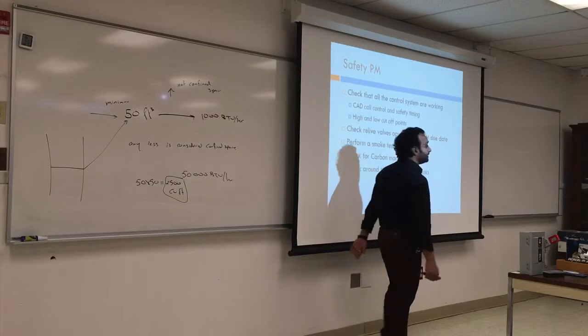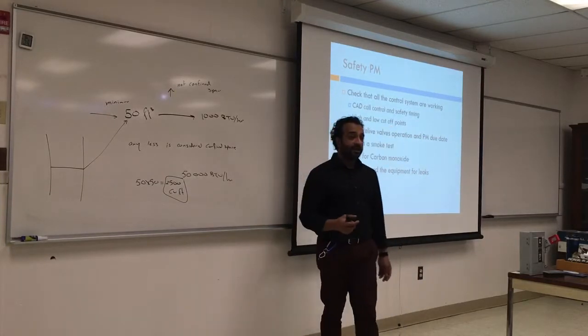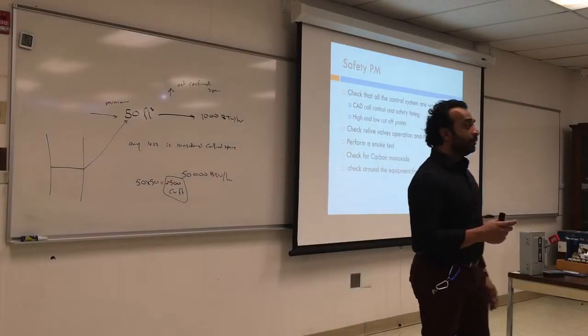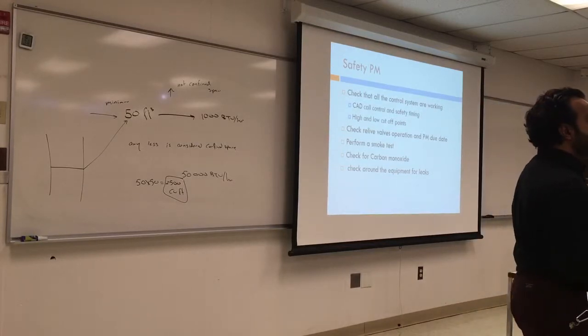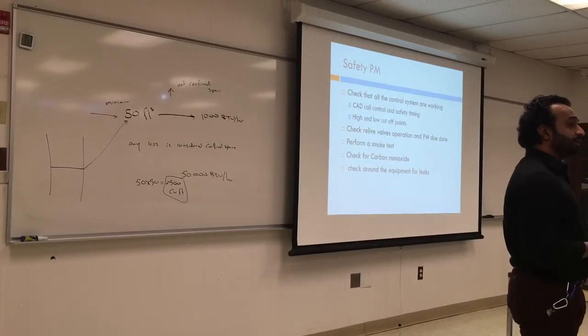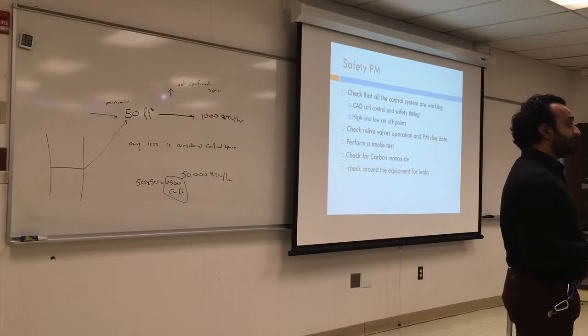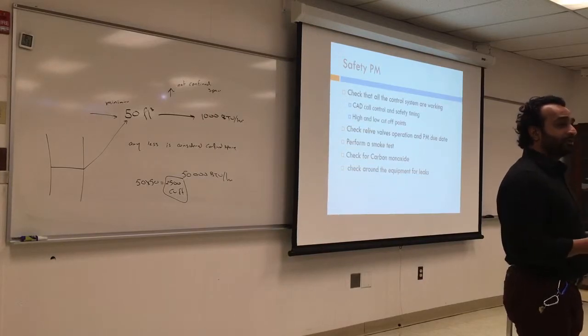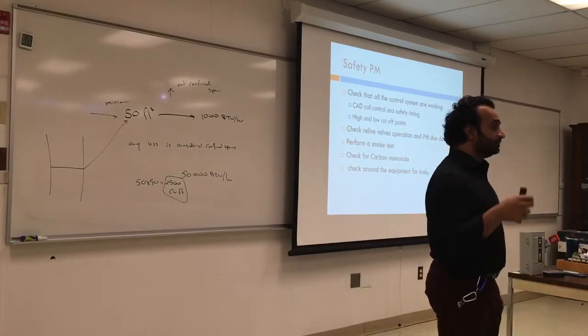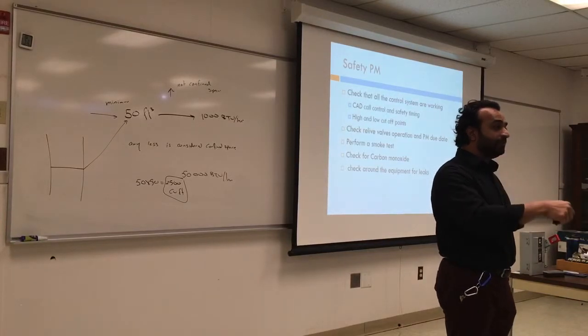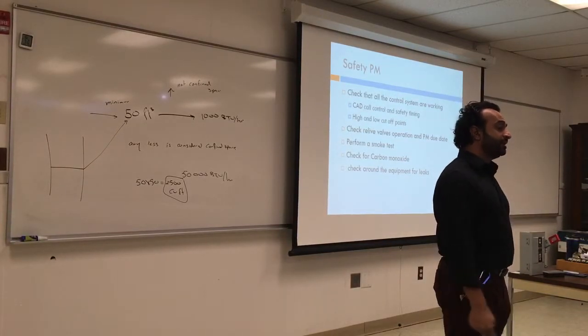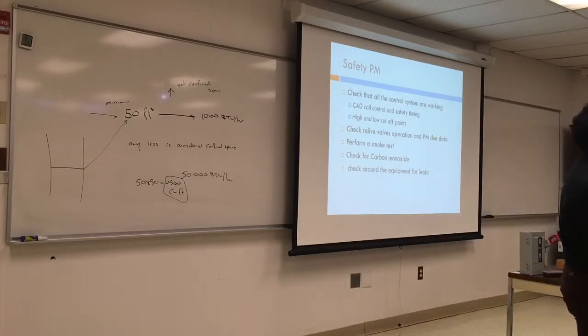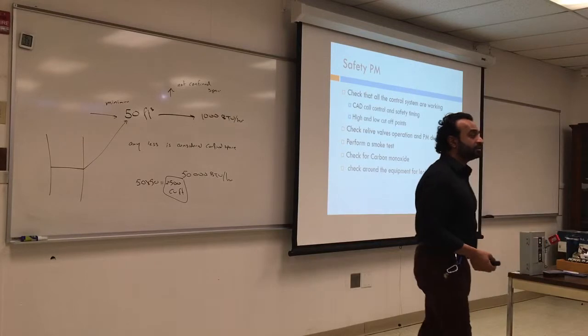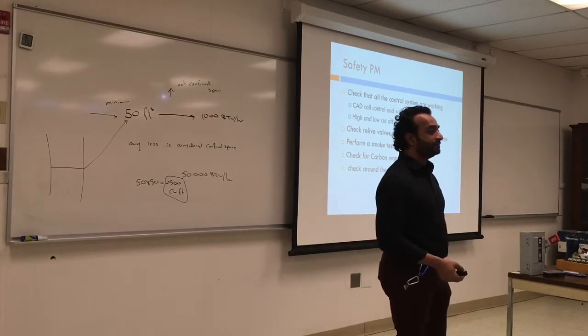Check the relief valve that it operates and it has been maintained. What is the expiration date on it and what is the last preventive maintenance? Every year you should turn on the steam, have it running, and check the relief valve. How do you check the relief valve? Press the lever, pull it, and it should let out some steam. If there is no steam, it's not going to have a lot of pressure, so it's not going to let the steam out.